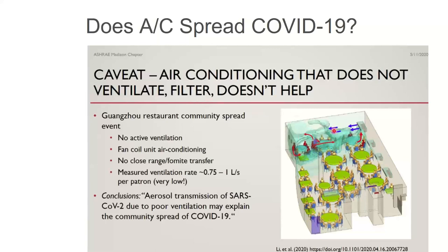If you can tell by this picture, these are all ductless mini splits in here. Ductless mini splits are fantastic for dehumidification control and tight temperature control and ease of installation. But what they're not good at is fresh air. And unfortunately, this facility didn't have much fresh air. 1 liter per second, which is 2.1 CFM per person. There is nowhere in our whole country that has a rate that low.